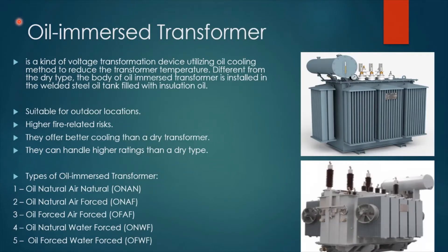The second type is the oil immersed transformer. It is a kind of voltage transformation device utilizing the oil cooling method to reduce the transformer temperature. Different from the dry type, the body of an oil immersed transformer is installed in a welded steel oil tank filled with insulation oil. An oil immersed transformer is suitable for outdoor locations. It has higher fire-related risks, which is why it should be installed outdoors. They also offer better cooling than a dry transformer and can handle higher ratings.